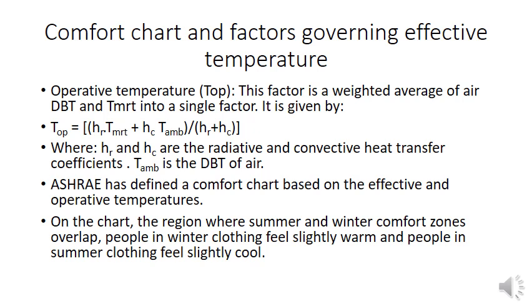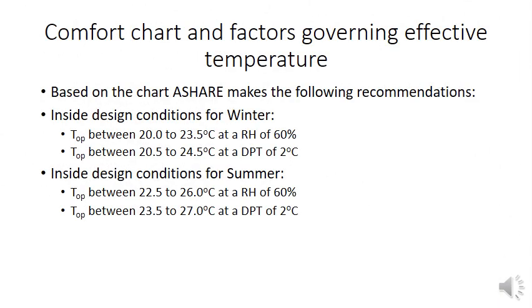Based on operative temperature, ASHRAE defined the comfort chart showing summer and winter comfort zones. For winter clothing, the comfort zone has an operative temperature between 20.0°C and 23.5°C with relative humidity of 60%; a more precise range is 20.5°C to 24.5°C at a dew point temperature of 2°C. For summer, the range is 22.5°C to 26°C. These define the inside design conditions for winter and summer, including the relative humidity and dew point constraints.